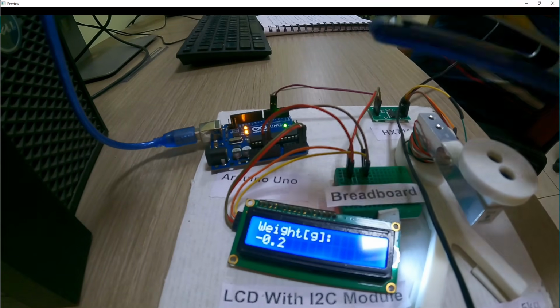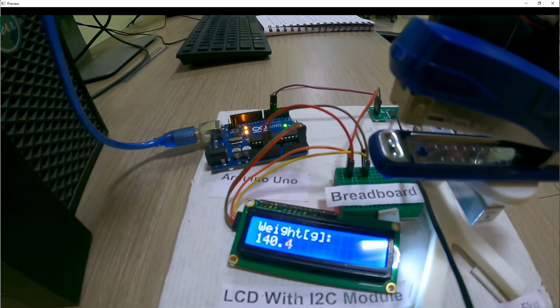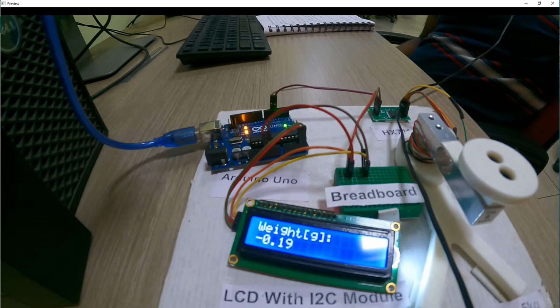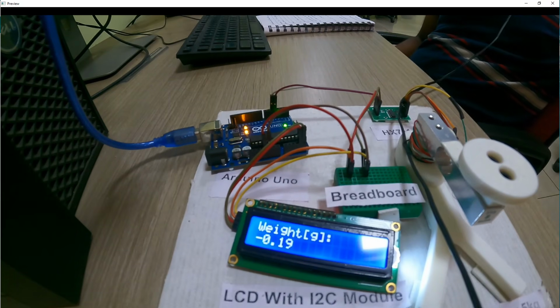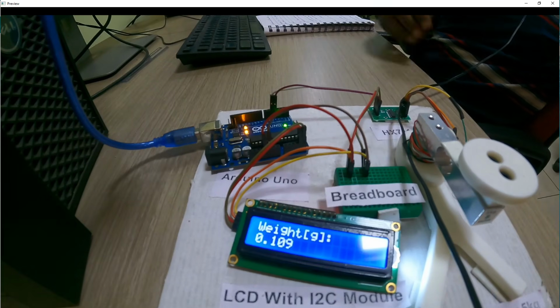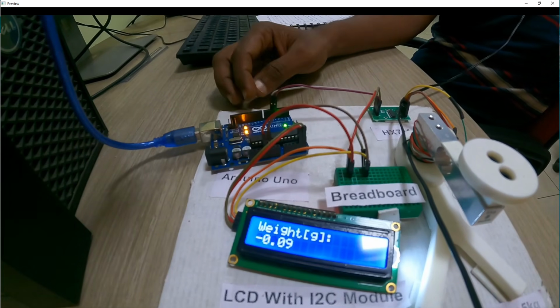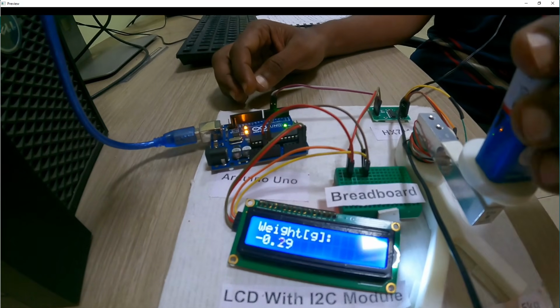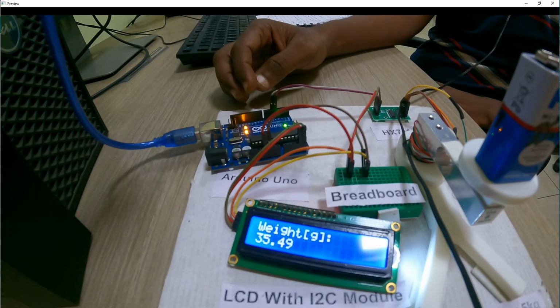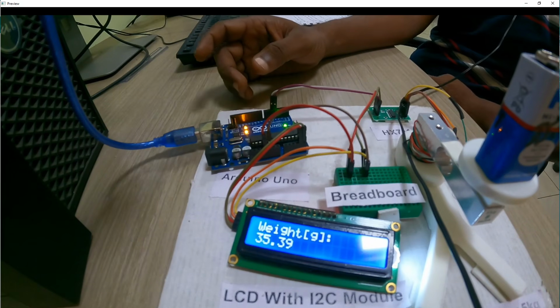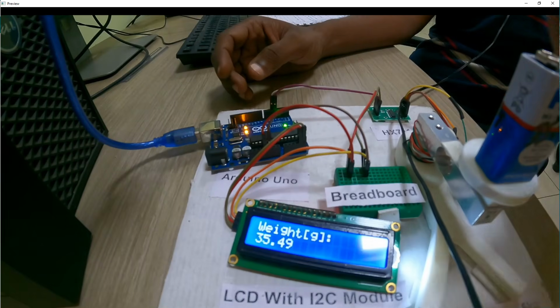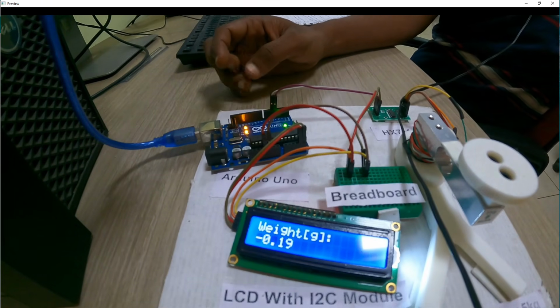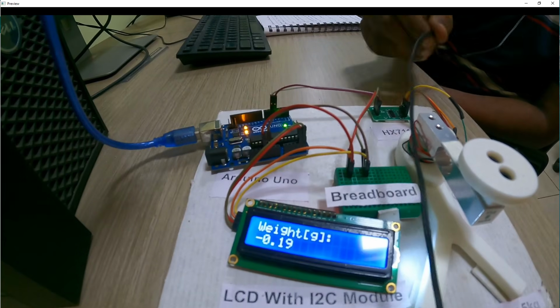Now if I place the stapler, you can see the weight is showing 140.4. Original is also 140.4. So that's it really. So if you set the tare as 0, it's almost 0 in any case. So this is 35.54. You can see that the weight is being measured pretty precisely. Okay, some 0.1 gram error, which is acceptable, which is well within the limits.